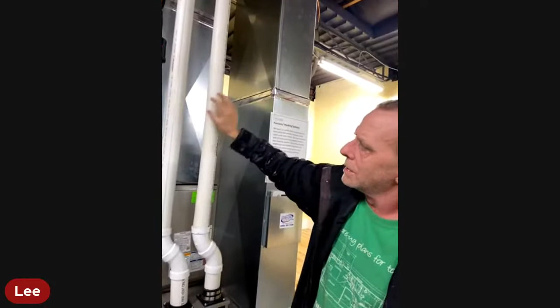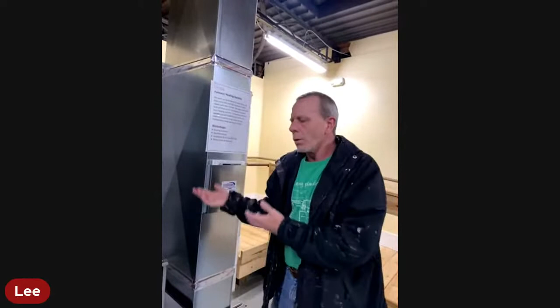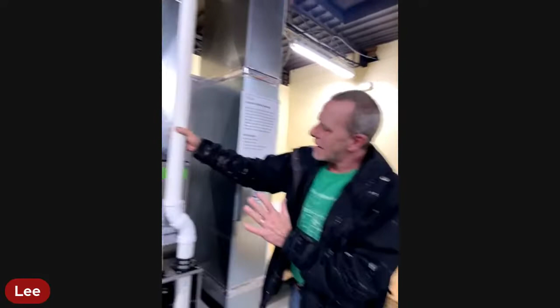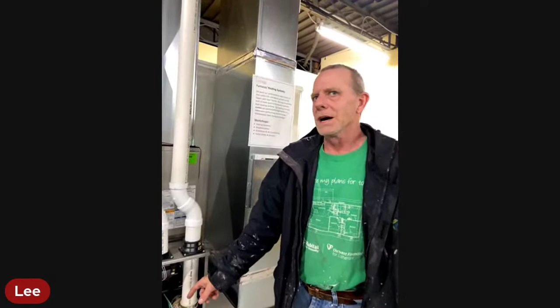Sometimes what will happen, and this happened to me, these pipes are sticking outside your house, and there's a lot of different varieties of how they stick out depending on when it was put in. One time I was doing my fall cleanup and had something like a hammock, and I leaned it up against those pipes without thinking about it. What happens is that when that first motor is running, it's making sure this isn't blocked, and it can be blocked anywhere down this line all the way to the outside. So it was getting enough back pressure blowing on whatever I set in front of it, where the computer says no, something's not right, and it would never turn on.